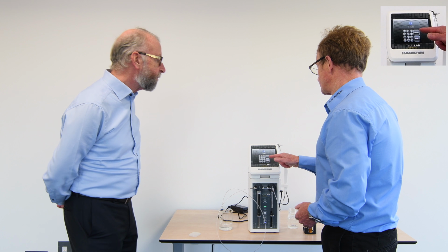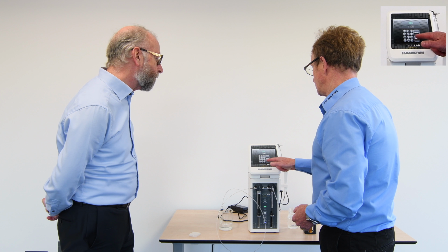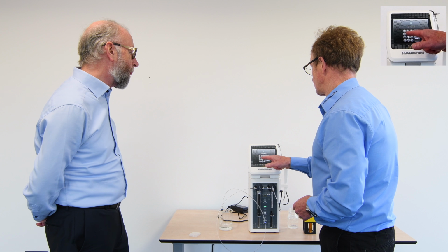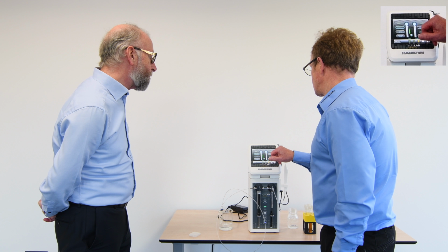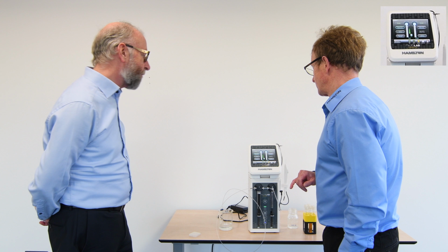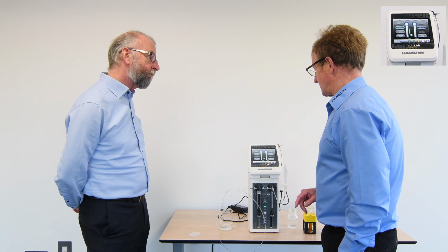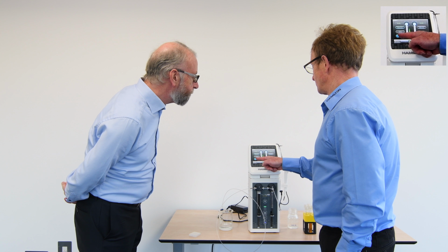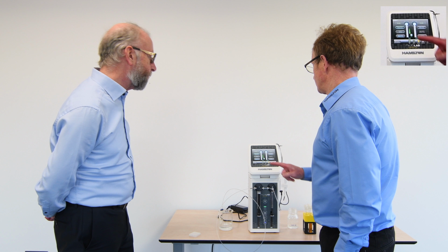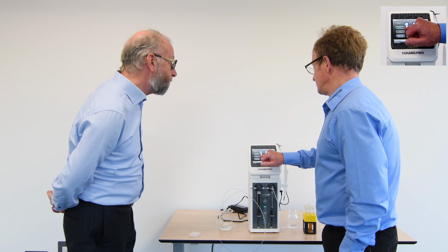So if I enter that and we're doing a 500 microlitre sample, and you were doing a 1 in 4, you said, or 1 in 5? That's 1 in 4. Okay, so it's there. You can see that it's corrected and shown that we have 500 microlitres of sample and 1500 microlitres of diluent. I may want to increase my volume of wash to, let's say, 5 mils. I could easily do that by putting a wash step of 5,000 microlitres, whatever volume we think is appropriate for the diluent. So here you can see all the variables have now been changed.